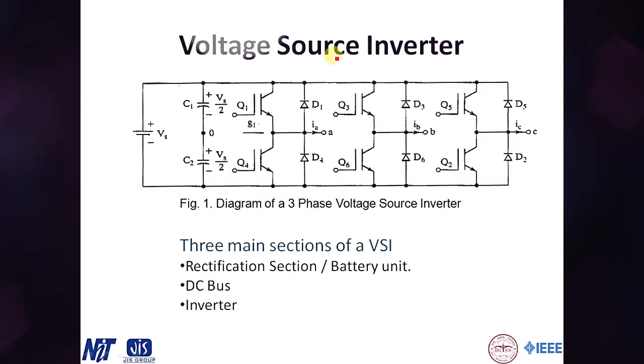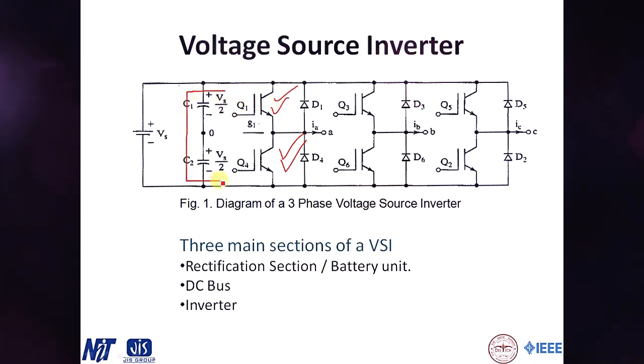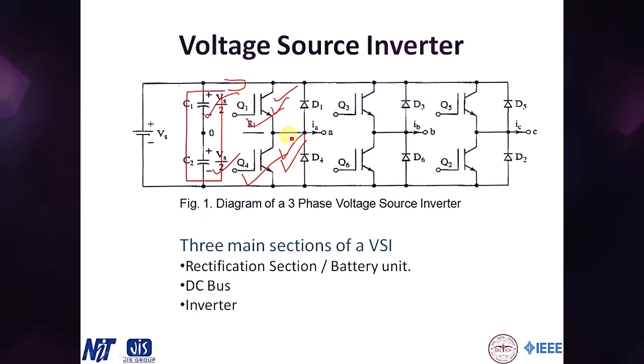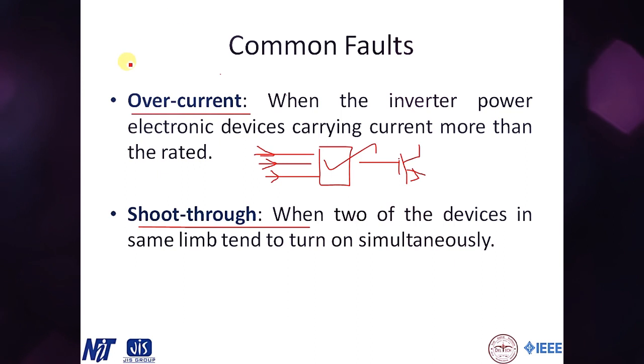Shoot-through happens when two IGBTs in the same limb conduct simultaneously — either both turning on at the same instant, or the lower one beginning conduction while the upper is still conducting. This short-circuits the DC bus, blowing up the capacitor and the IGBTs. This can occur due to a bad microcontroller program or electromagnetic interference, since these devices operate at very high frequency, causing IGBTs to turn on simultaneously because they haven't discharged properly.